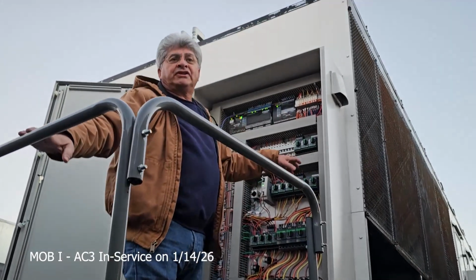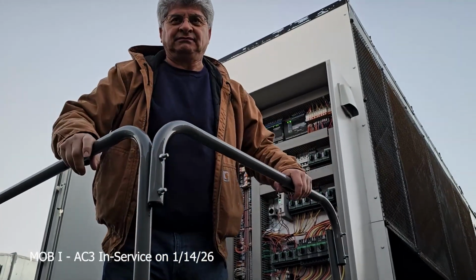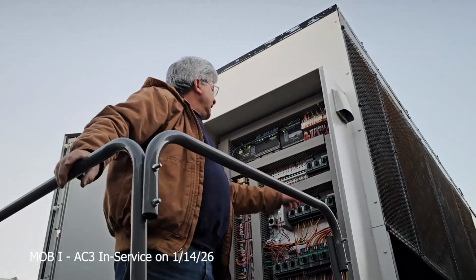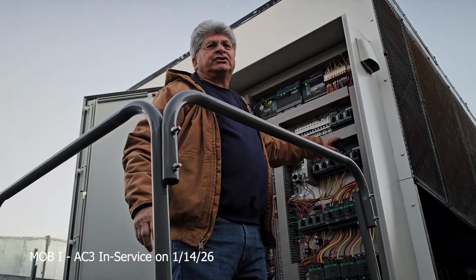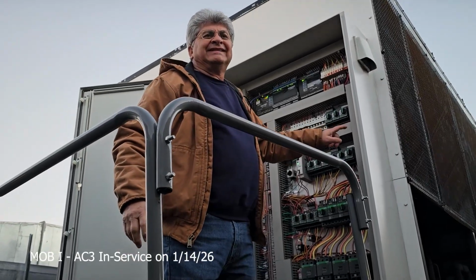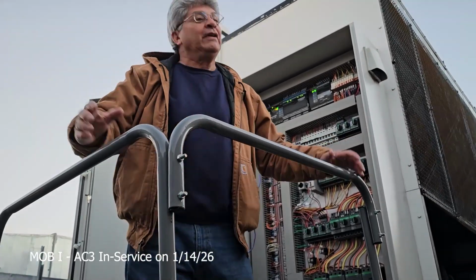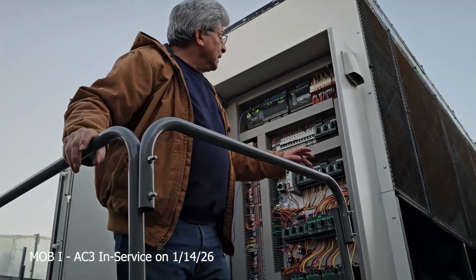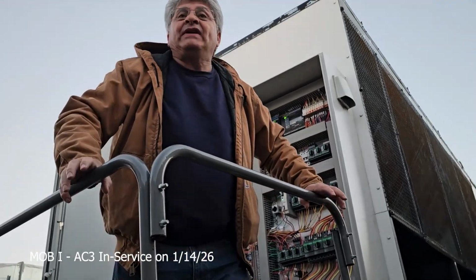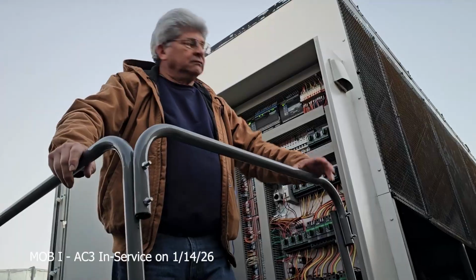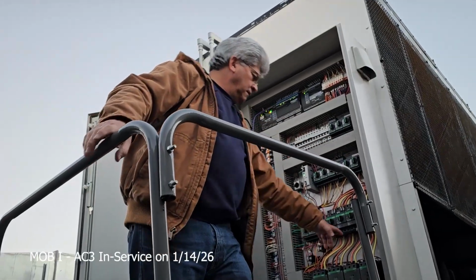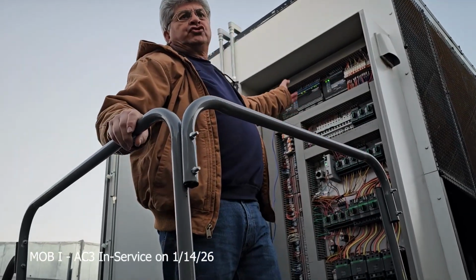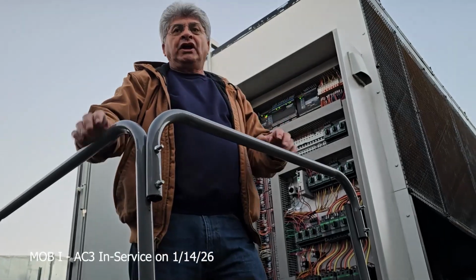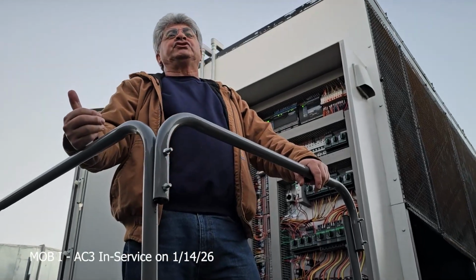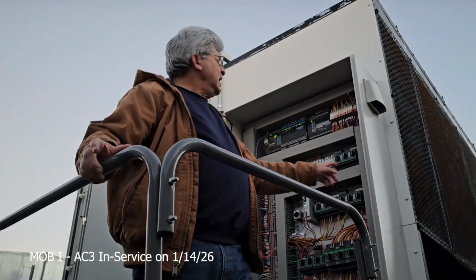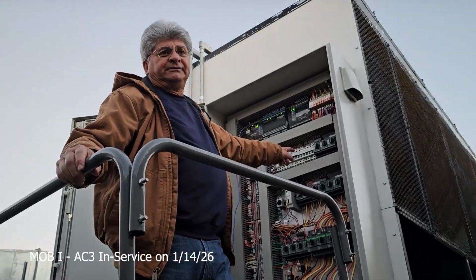The only time I write stuff is inside if I'm asked to, because they had me replace this plastic panel on a job because I wrote stuff down. So I'll write anything you guys want. Yeah, we won't do that here. But if you have an actuator go down, you want to ensure your high voltage is shut down, control voltage. So none of your fans will run, but your actuators will always still be live unless you turn that circuit breaker off.